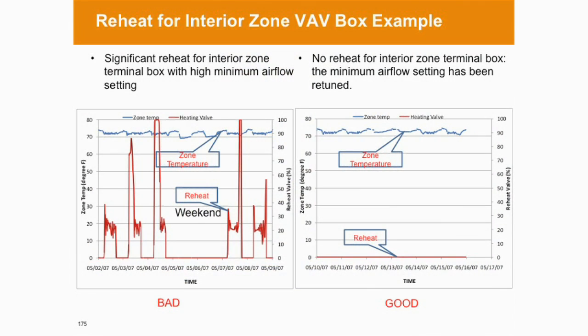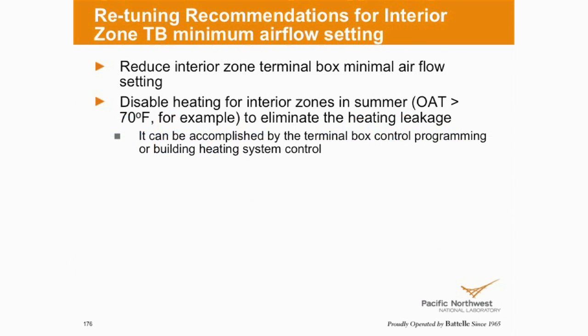After retuning, you can see that the reheat has been eliminated for that zone. That means you can achieve fan power savings through reduced airflow, reheat savings, and also cooling savings. So we want to reduce the interior zone terminal box minimum airflow set point. Some places may just disable the heating for the interior zone in the summertime, to eliminate heating leakage.